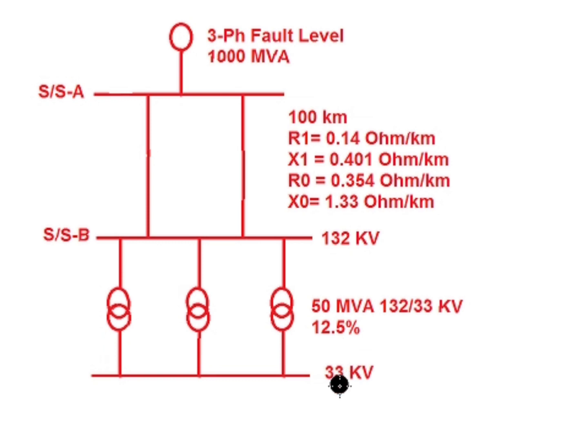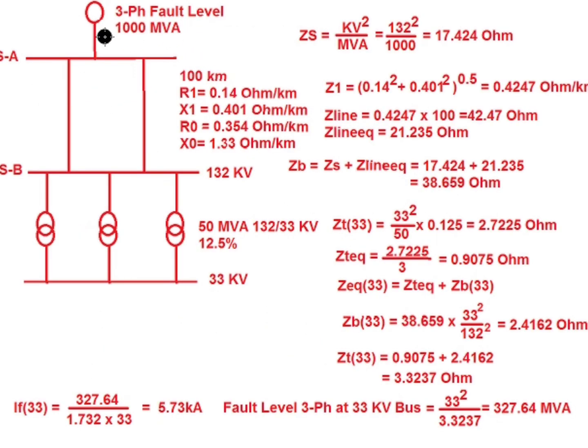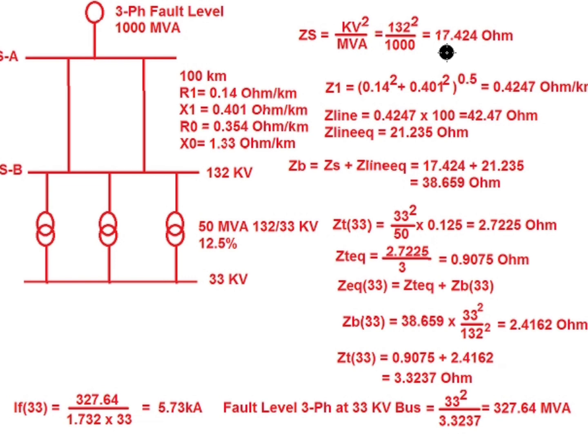We need to find the fault level at the 33 kV bus, given that the fault level at substation A is known. Since the three-phase fault level at substation A is 1000 MVA at the 132 kV bus, we can calculate the source impedance: Zs = kV² / MVA = 132² / 1000 = 17.424 ohm.